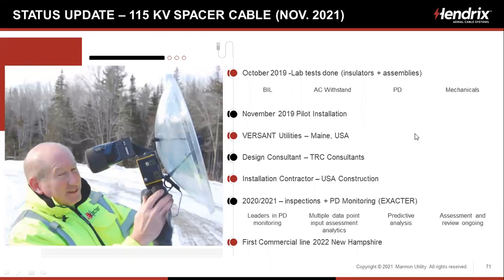Our design team in Milford at Hendrix figured this out. So by 2019, they had all the lab tests done. They had the insulators figured out. They had the assemblies figured out. They had done the BIL test, the AC withstand test. We did all sorts of testing on partial discharge, all sorts of testing on mechanicals.